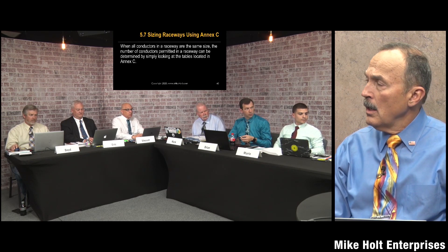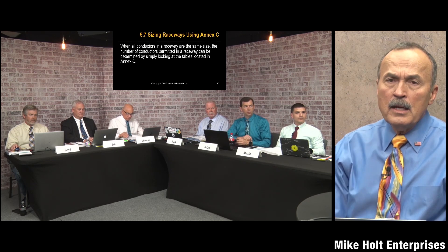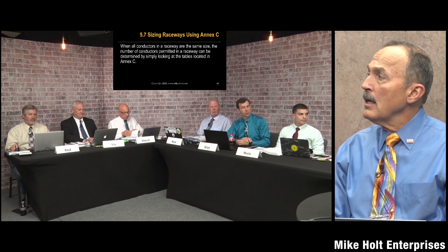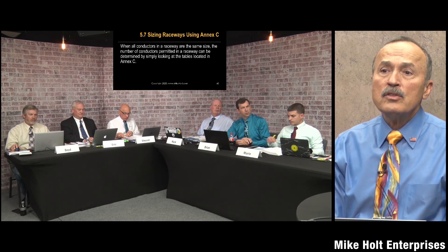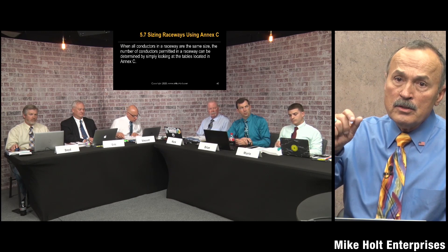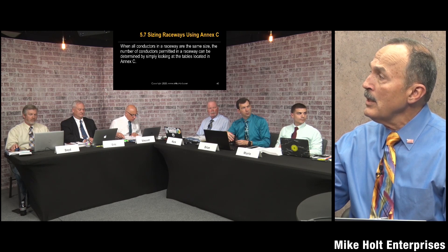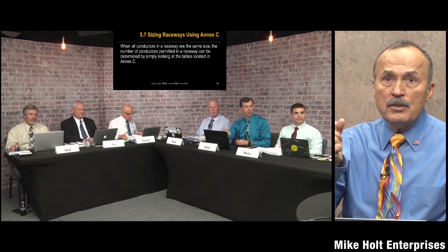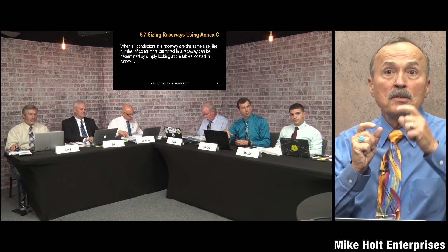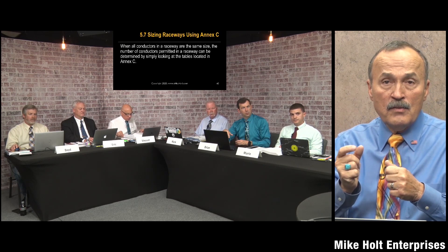Ryan, who works with us, had 300 KCMIL XHHW and wanted to find out how many could fit in a 2-inch raceway. You take the XHHW 300 KCMIL, go to Chapter 9 Table 5, find the area of the conductors. Then go to Table 4 - Schedule 40 PVC - find the area at 40% fill, then divide the conductor area into the conduit fill area.